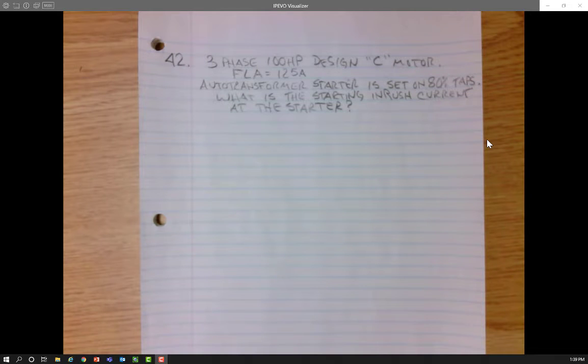The question is, I have a three-phase 100 horsepower design C motor, so the rotor design is C. It has a full load amps or full load current of 125 amps. It is connected to an auto transformer reduced voltage starter that is set on the 80% taps. And what we want to know is what's the starting inrush current at the starter.